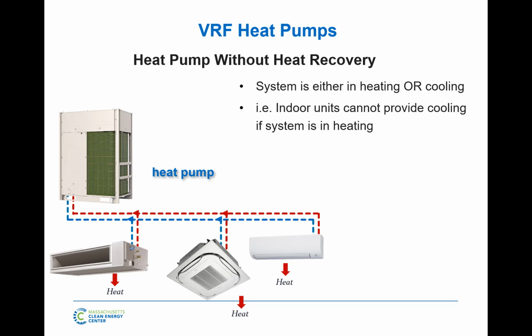I don't have just one chiller for the whole building that I turn on and off. I've got multiple systems. Some buildings can have 50 VRF systems. That happens. If we're talking about a 1,000 suite hotel, which exists out there with VRF, there's multiple systems and they're all zoned. The other advantage too is I don't need to go turn a chiller on and turn a boiler on and turn it off. This will switch over automatically, because this condenser knows exactly what's going on in each unit.